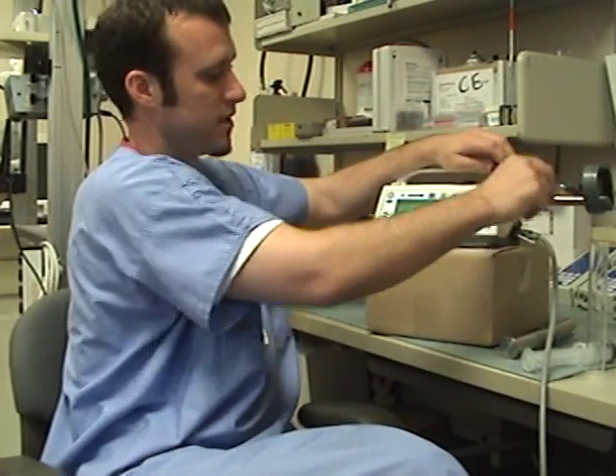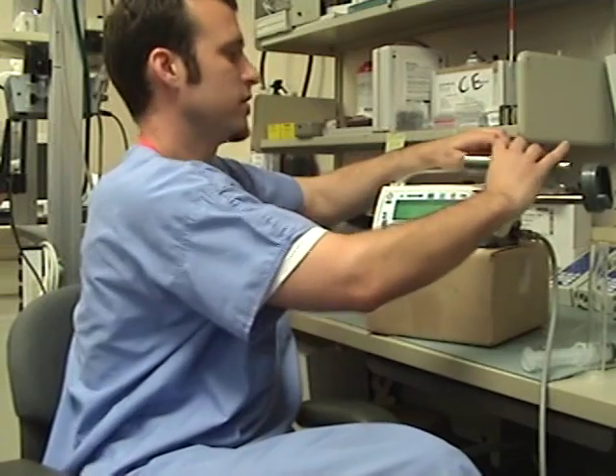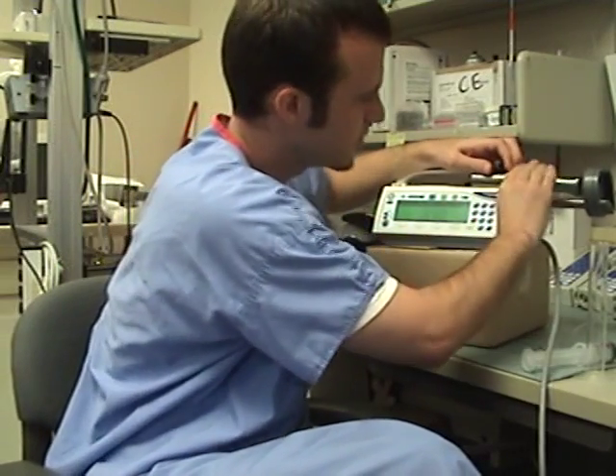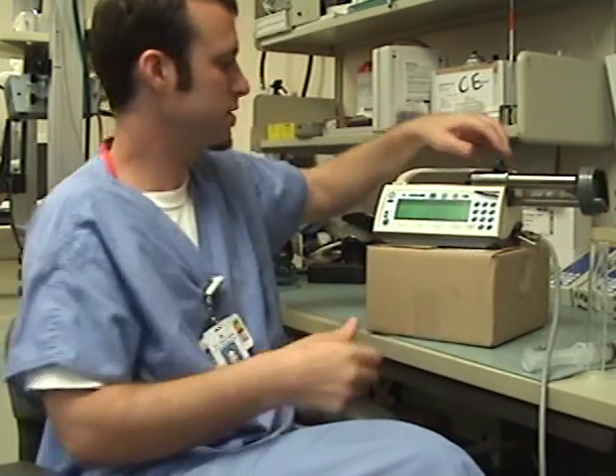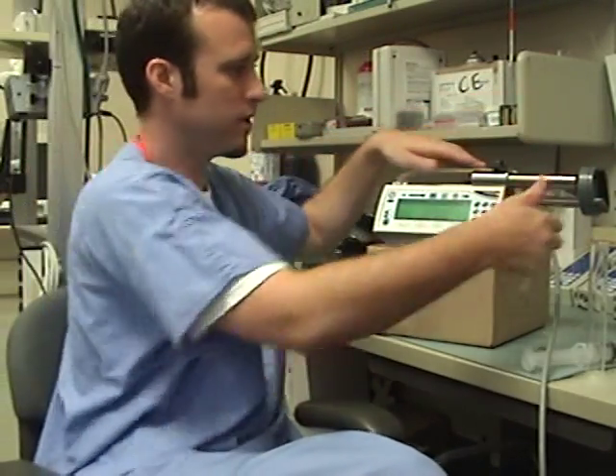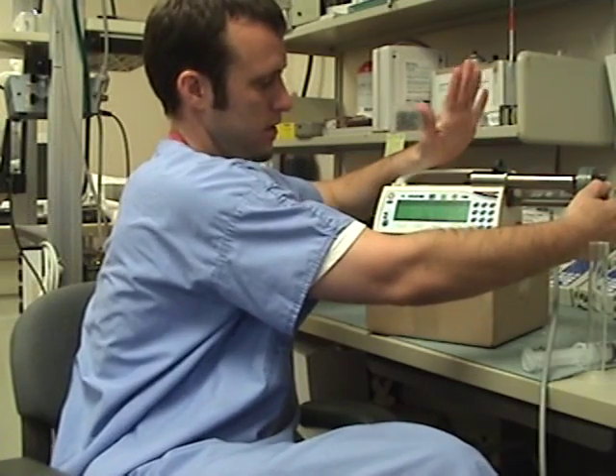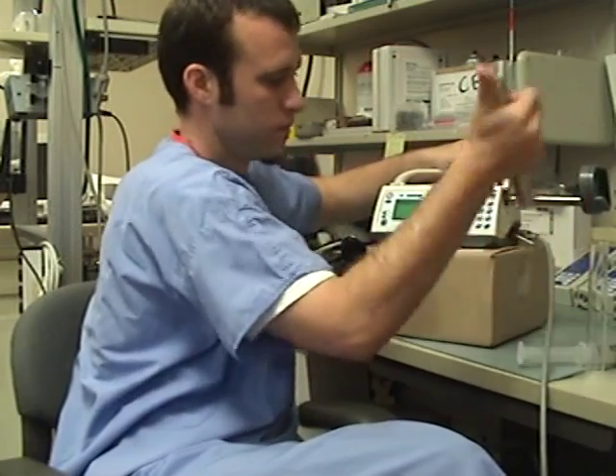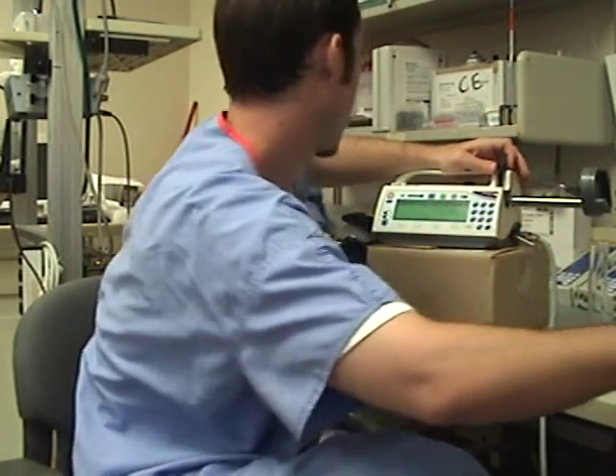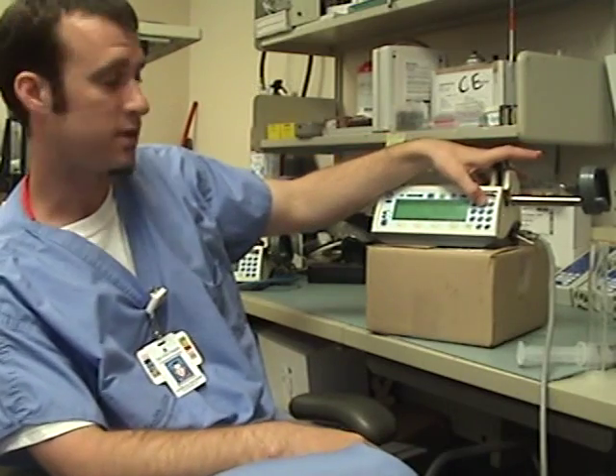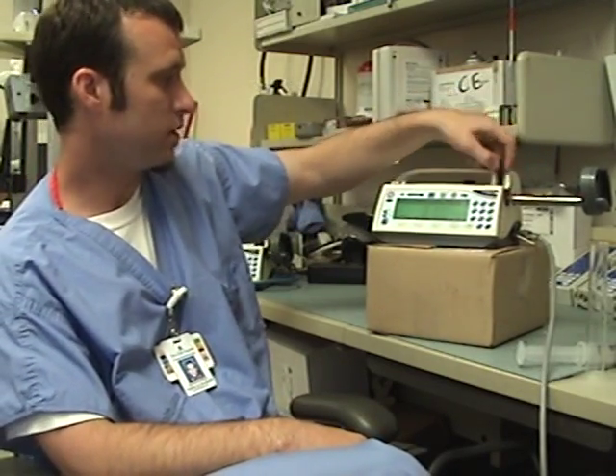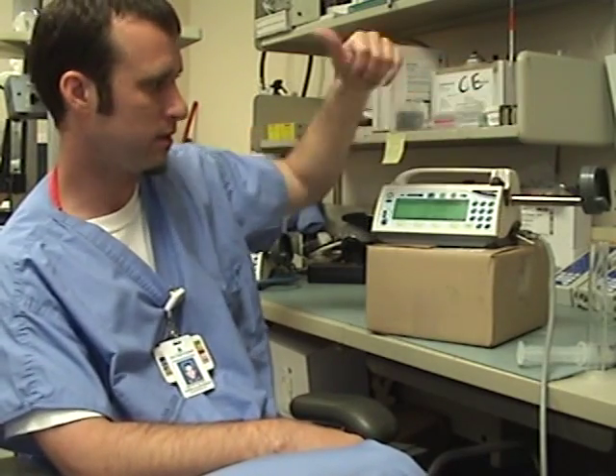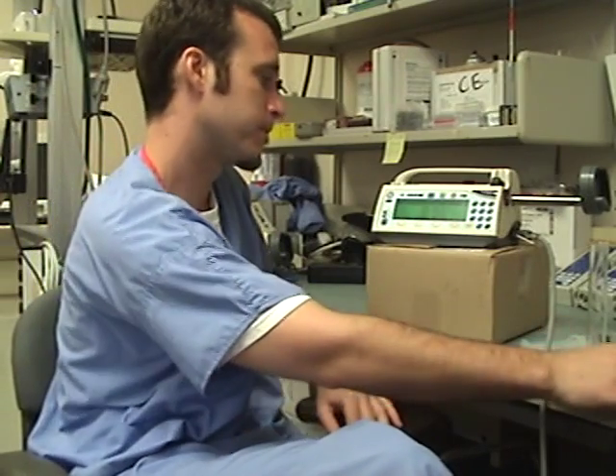From here we have to set up the high side standard. It requires the larger calibration plug. Once again, ensure that it is placed in just as you would a syringe. Mount it, hit continue, open your plunger arms, hit continue again. Our next step is going to be to calibrate the force sensor. From here, we leave the pump open, nothing impeding, nothing pushing on the force sensor, and we hit continue. The unit runs through and auto zeros the force sensor. When it's done, it'll come up on the screen to let us know.